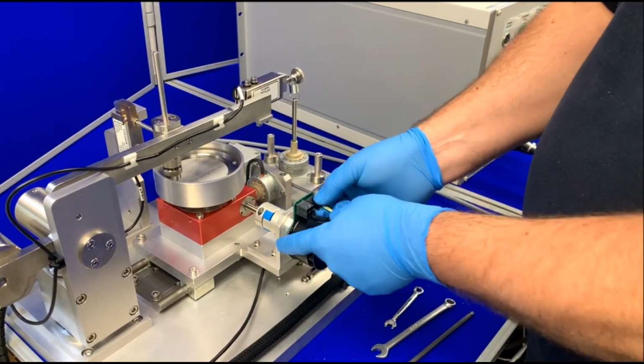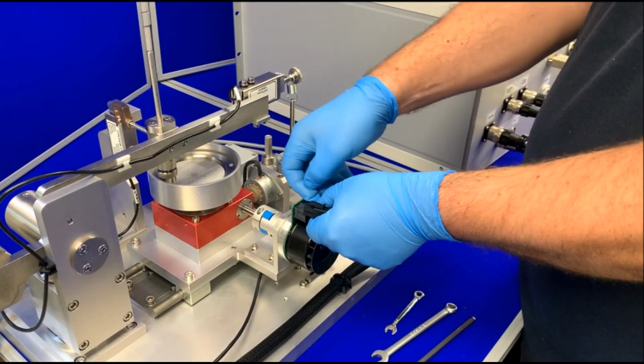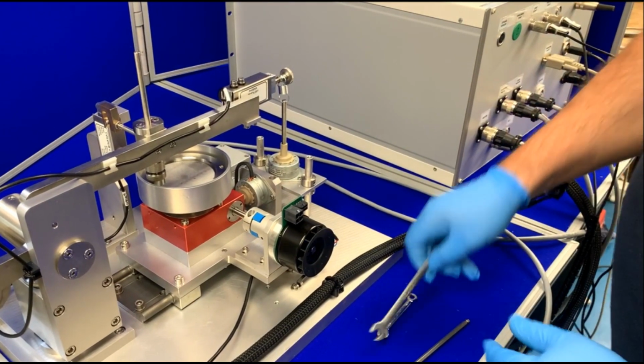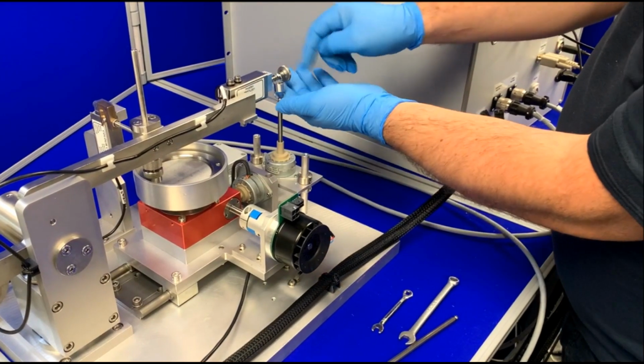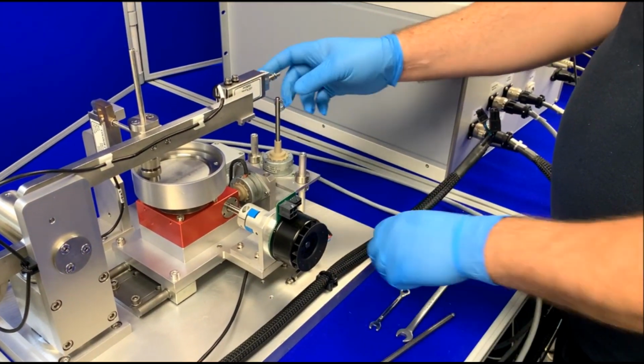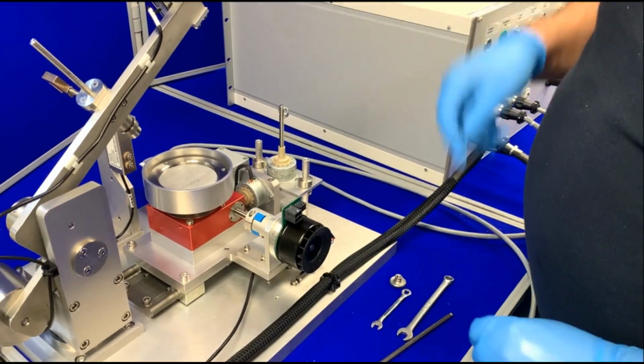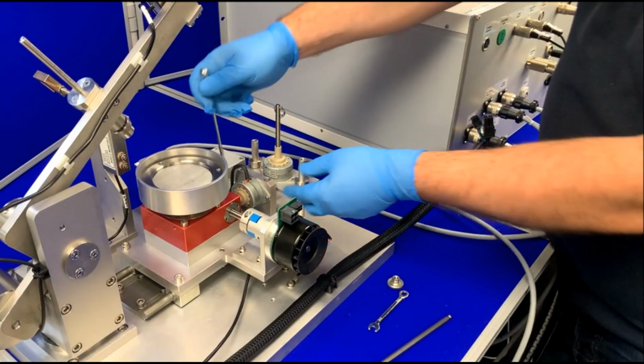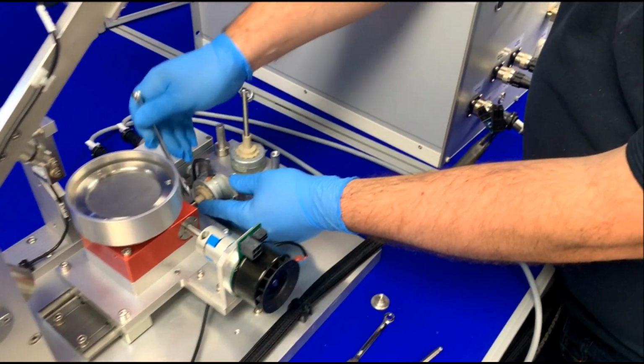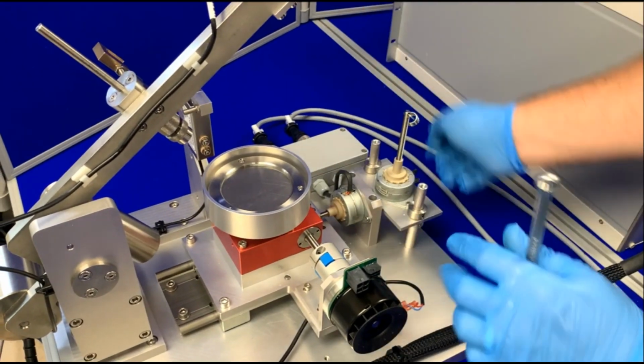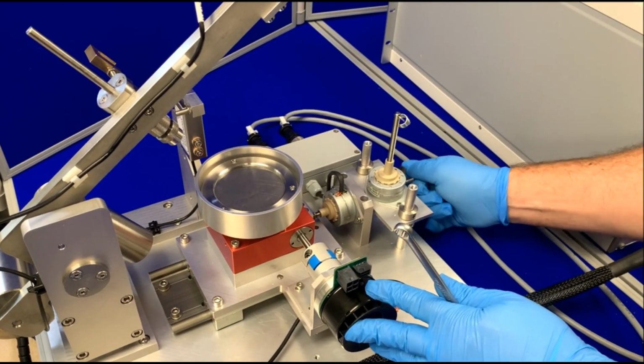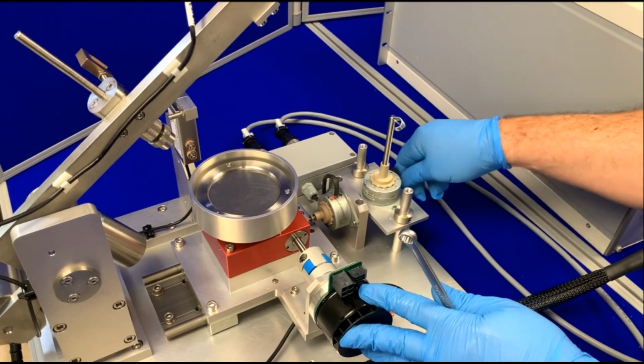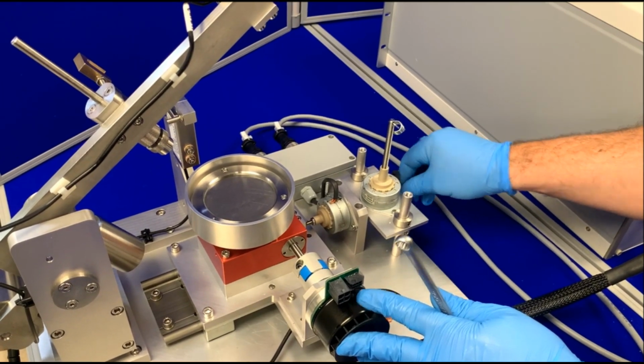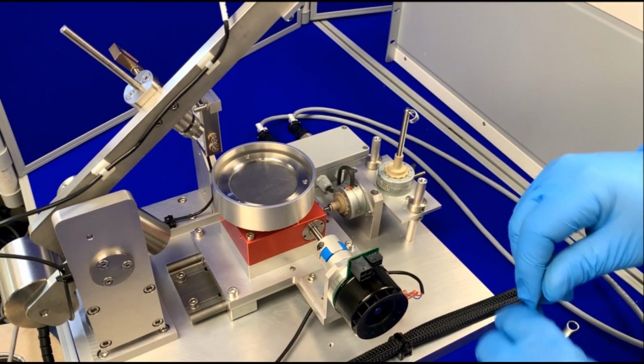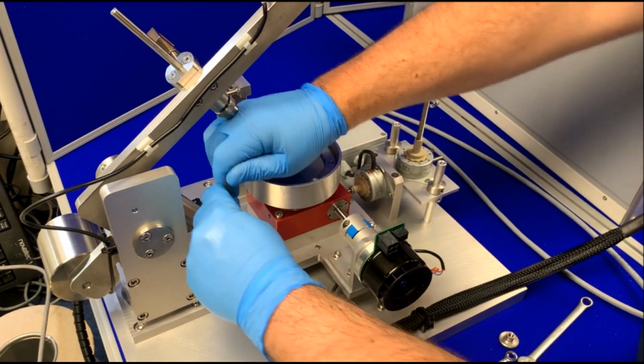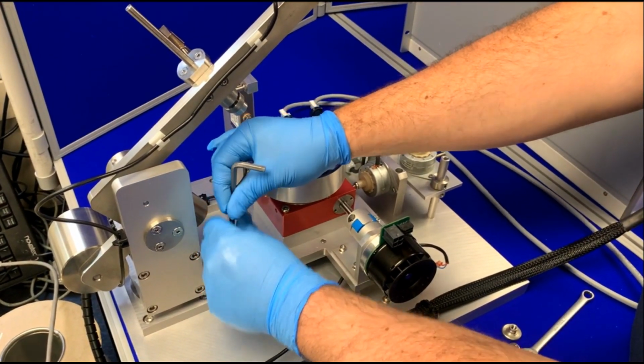To remove the pin on disc adapter, start by disconnecting the motor and Hall effect sensor cables. Unscrew the load knob and slide off the spring. Lift the load beam. Using a spanner, release the screws securing the indexing motor lead screw from the carriage. Unwind the lead screw to free the carriage, and use an Allen key to unscrew the 4 screws securing the adapter to the base plate.